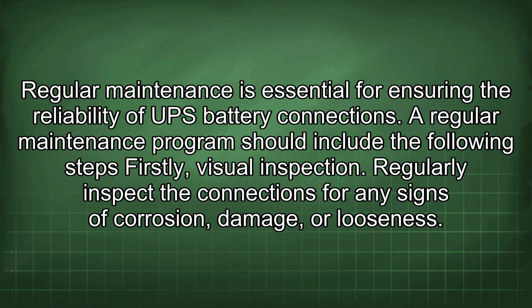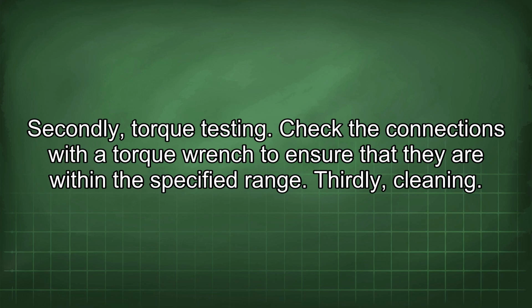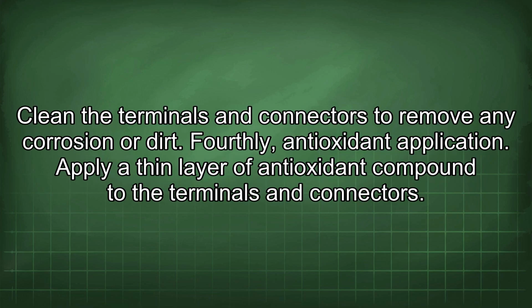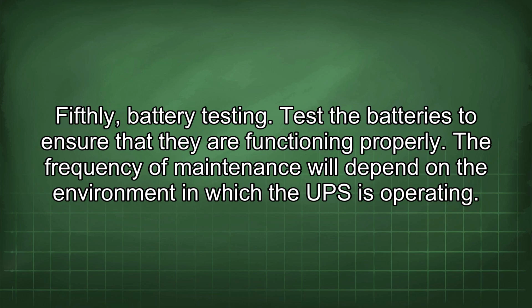Regular maintenance is essential for ensuring the reliability of UPS battery connections. A regular maintenance program should include the following steps. Firstly, visual inspection. Regularly inspect the connections for any signs of corrosion, damage, or looseness. Secondly, torque testing. Check the connections with a torque wrench to ensure that they are within the specified range. Thirdly, cleaning. Clean the terminals and connectors to remove any corrosion or dirt. Fourthly, antioxidant application. Apply a thin layer of antioxidant compound to the terminals and connectors. Fifthly, battery testing. Test the batteries to ensure that they are functioning properly.